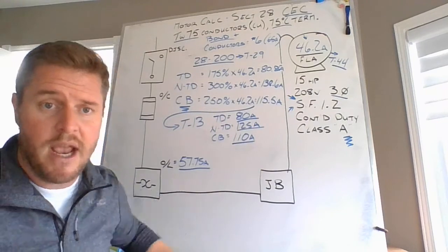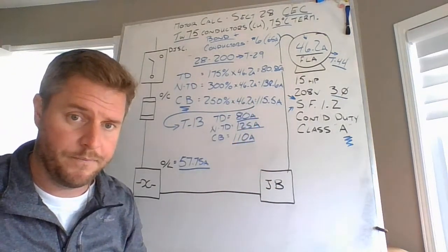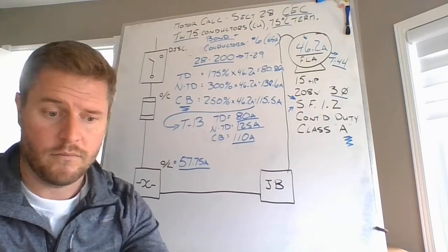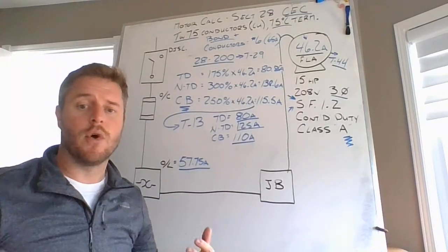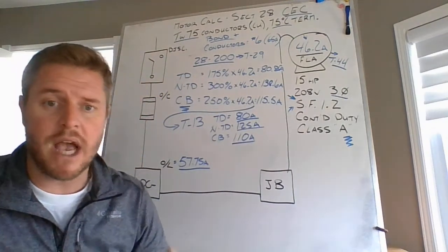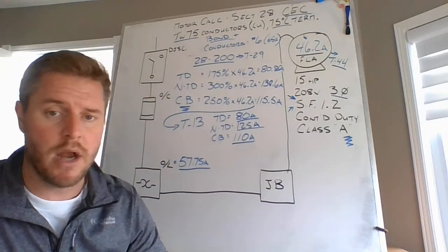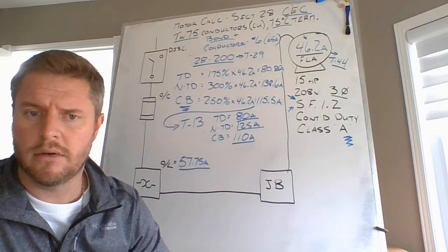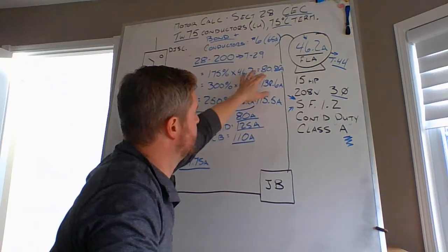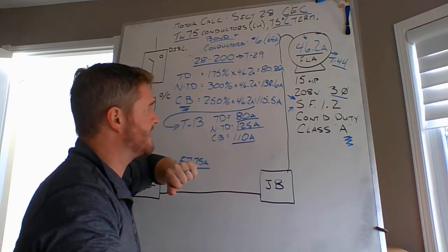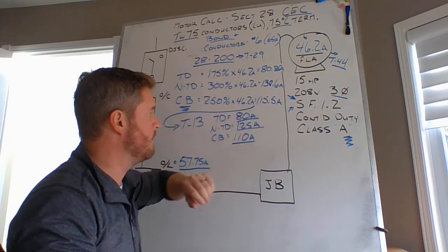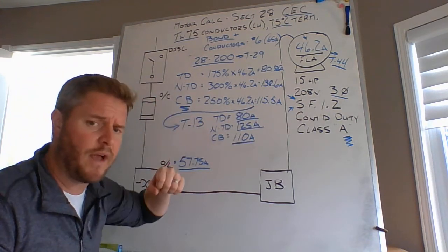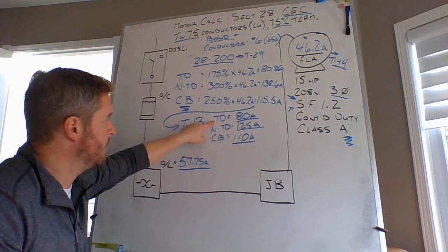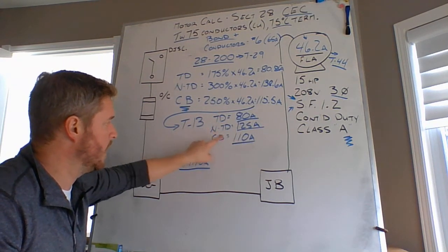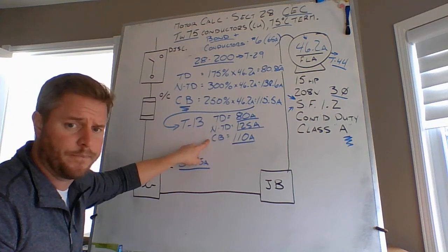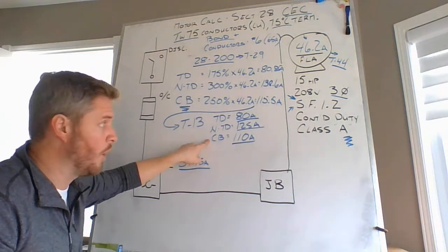Now would be a good time to hit pause, and everything is based on the full load current rating of the motor. Okay, so based on the full load current rating of the motor, I size my overcurrent protection, whether it's a time delay, a non-time delay, or a circuit breaker. All right, and I came up to my calculated values being 80.85, 138.6 amps for a non-time delay, 115.5 for a circuit breaker. My installed values are 80 for a time delay, 125 for a non-time delay, and 110 for a circuit breaker. Good things to know.